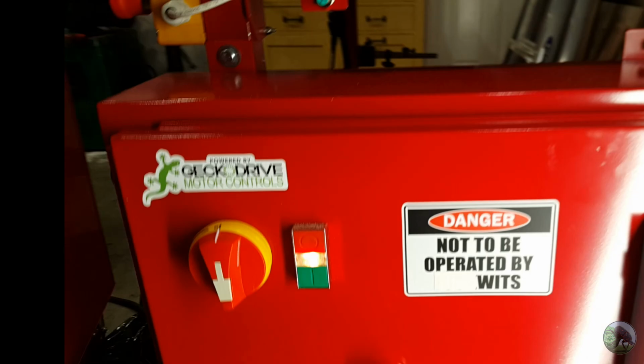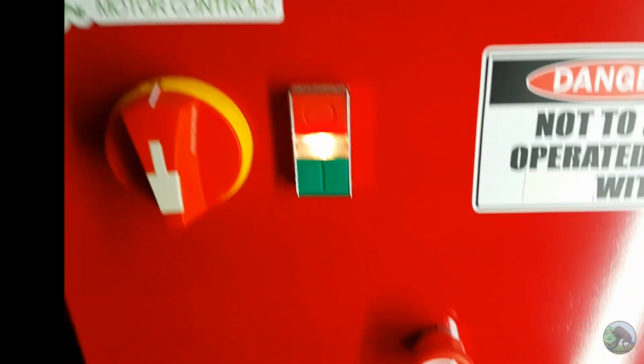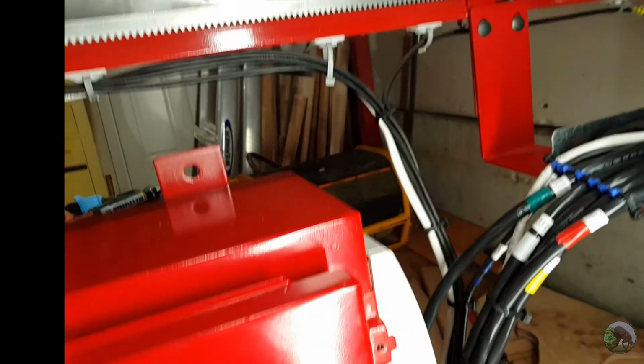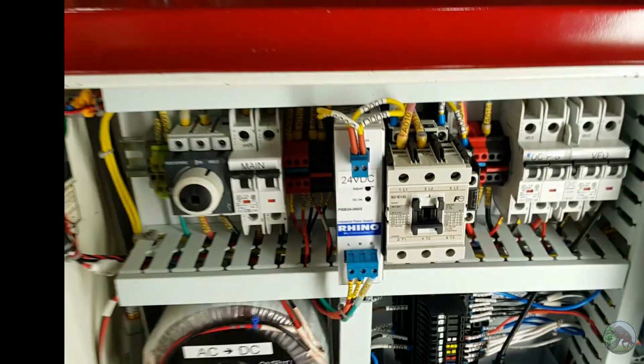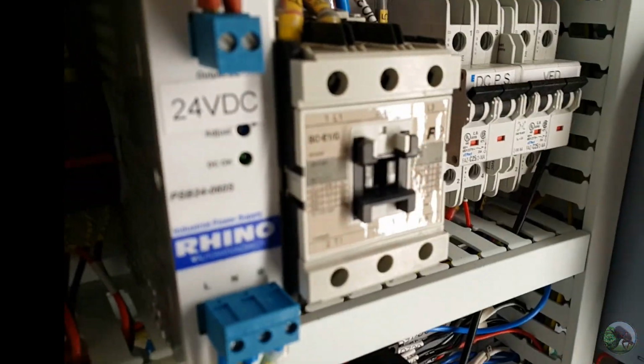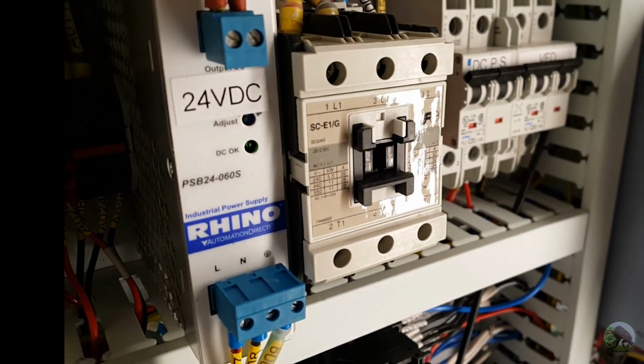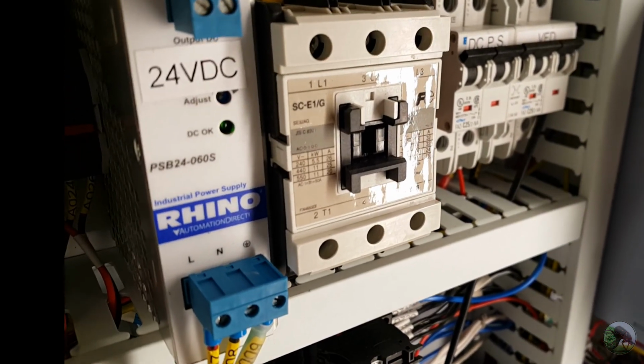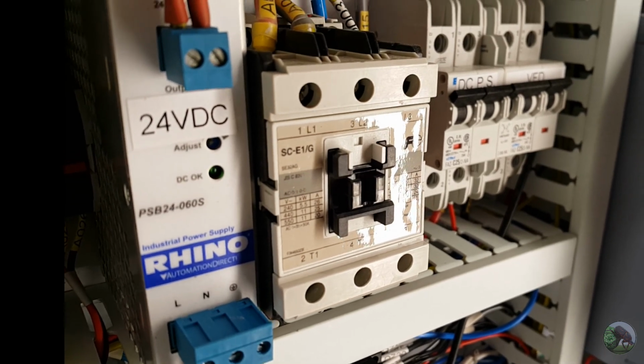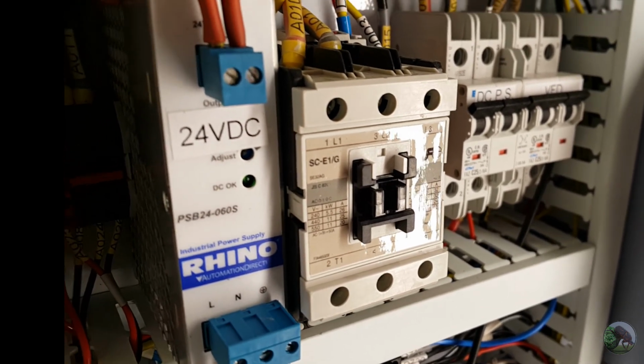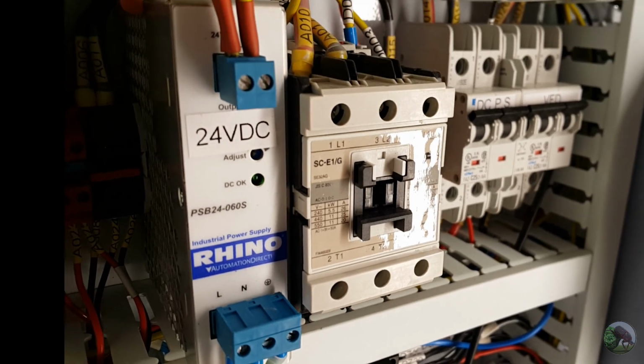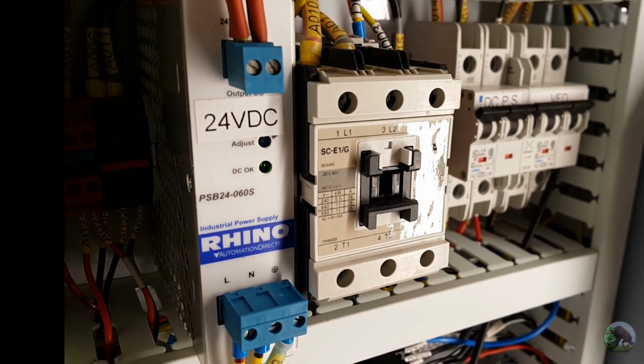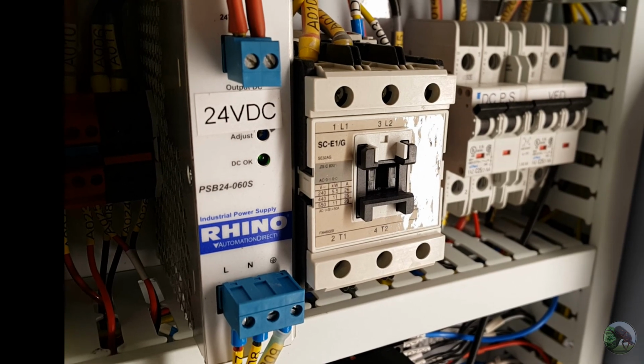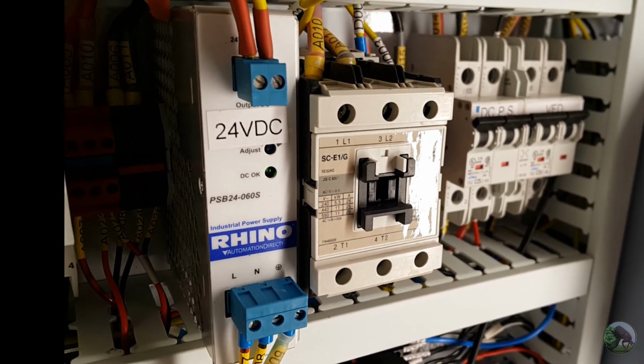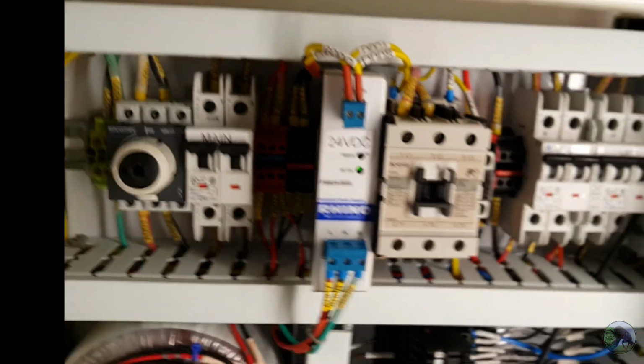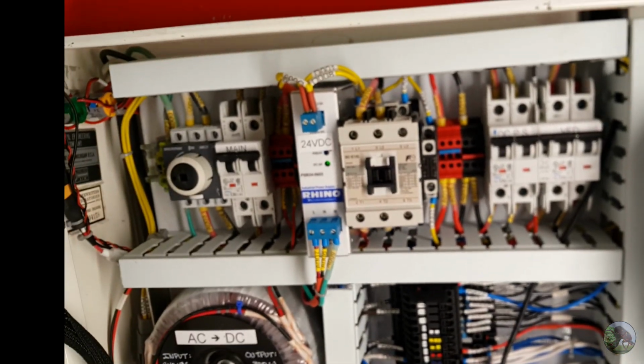You also heard the stepper motors power up. And so essentially, if we look inside, one of the things you'll be able to see is if I turn off that switch by hitting the red button, the contactor will open. So that's the contactor moving. Now I'll turn the power back on. So that the coil, which is a 24 volt DC coil in there, is being activated. It's pulling that contact in and basically turning on the power to the rest of that circuit.